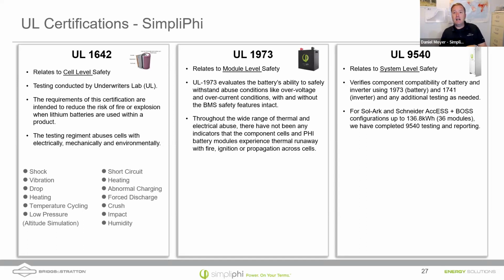Once you get a UL 1973 module, you can then put it into a 9540A system level certification. And how you achieve that is you really have to pair it with a listed inverter, 1741SB inverter now, and a 1973 battery, and then integrate them into the system level.